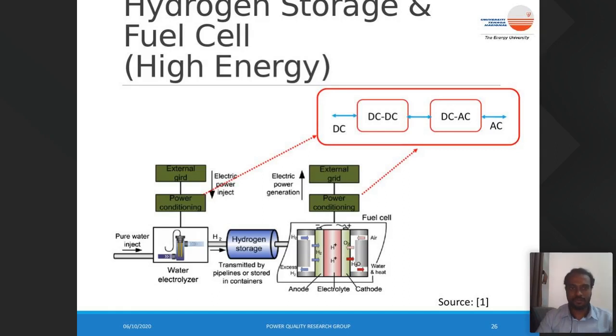This is a combination of two or three subsystems where we have an electrolyzer, a hydrogen storage, and a fuel cell. The electrolyzer operates as a charging device where it consumes electricity from the grid and electrolyzes the water, splitting the water into hydrogen and oxygen. The generated hydrogen is stored in a compressed or pressurized hydrogen storage, and the stored hydrogen is used to generate power using a fuel cell when there is a need in the grid.